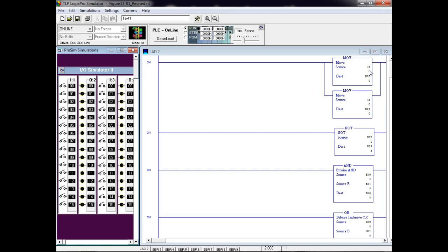So I have to tell Siemens to input a word. So we have a way we can tell it to input a word. But if I just put an input port on the Siemens PLCs, then it's going to go out there and bring in a what? 8 bits. So Siemens PLCs works with bytes. Allen-Bradley's PLCs work with words.